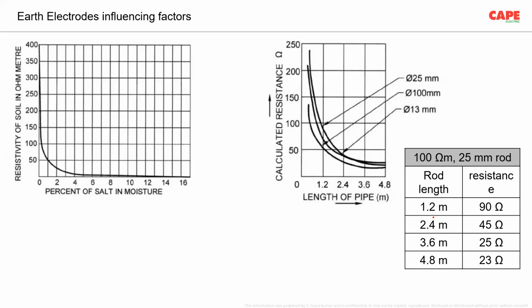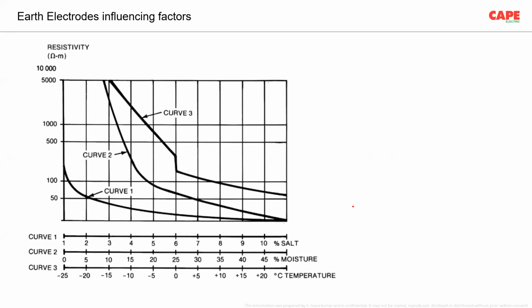Now, in a typical 100 ohm meter soil with a 25 mm rod, from this table we see that if the length of the rod is 1.2 meter, you simply calculate 100 divided by 1.2, which is approximately 90 ohms. So 2.4 meters gives 45 ohms, 3.6 meters gives 25 ohms, and a 4.8 meter pipe or rod in soil will give a resistance value of 23 ohms. These tables are also there in IS 3043.